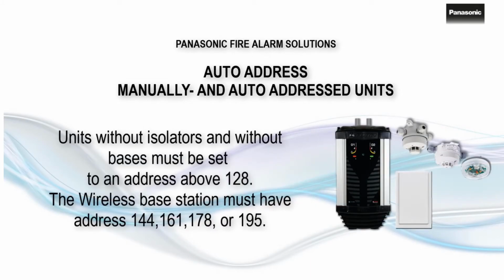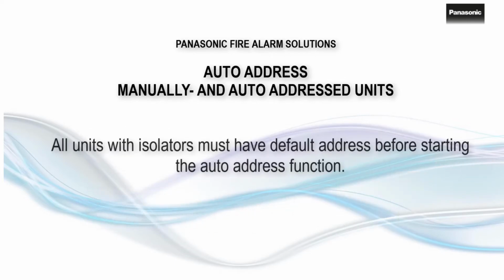Units without isolators and without bases must be set to an address above 128. The wireless base station must have address 144, 161, 178, or 195. All units with isolators must have default address before starting the auto-address function.